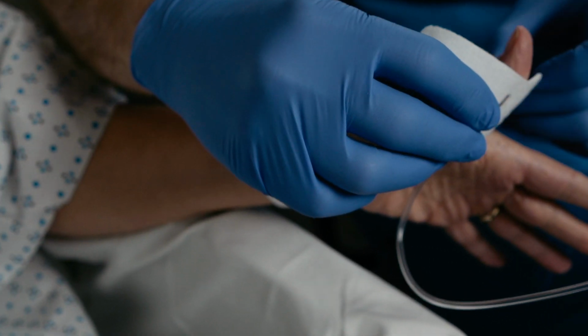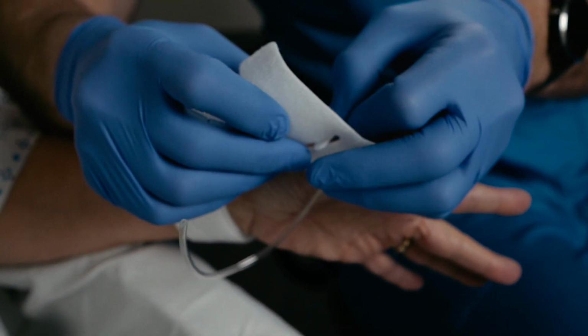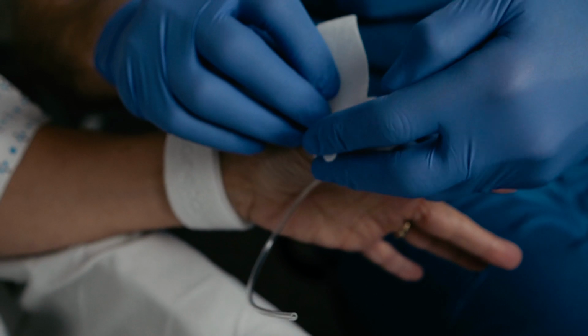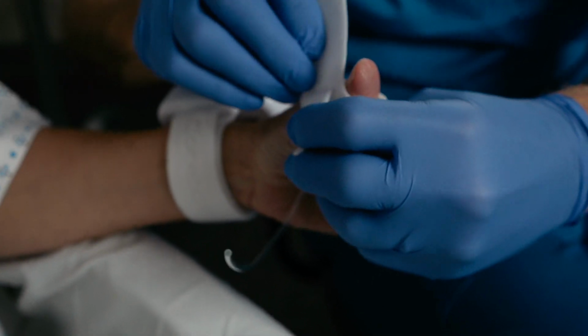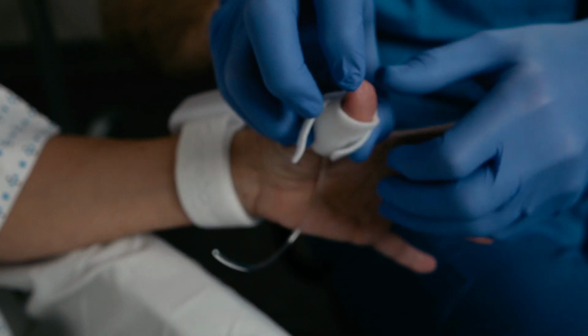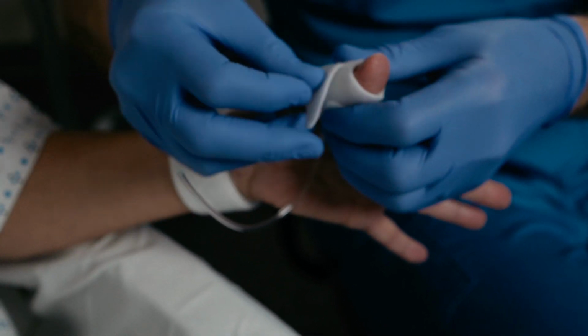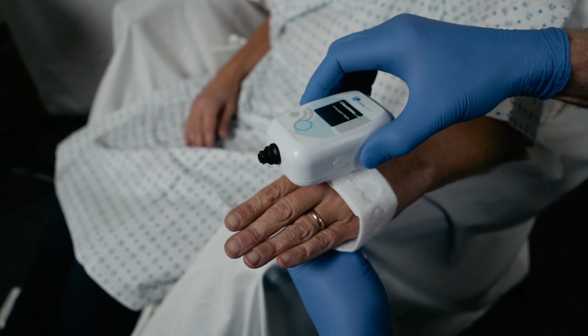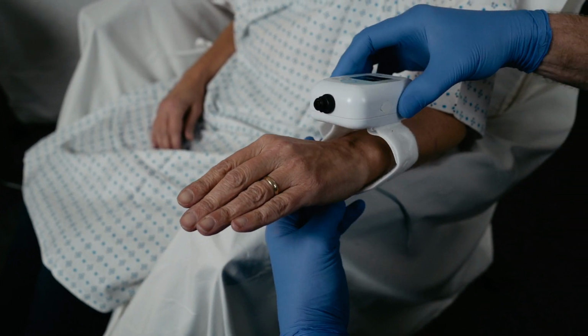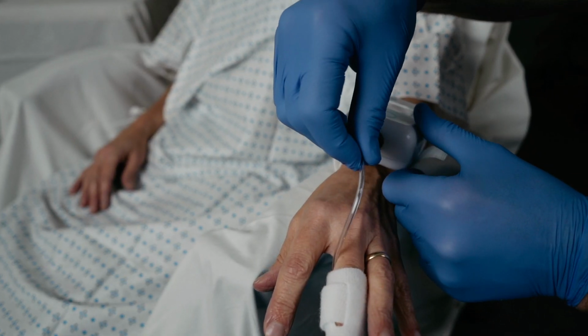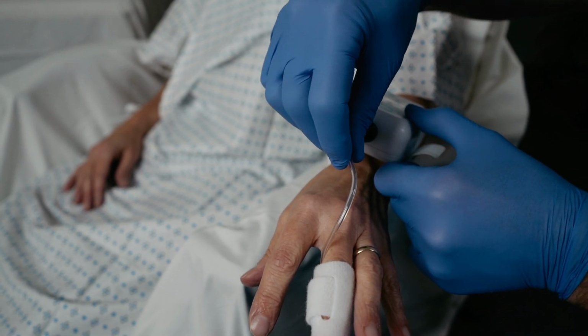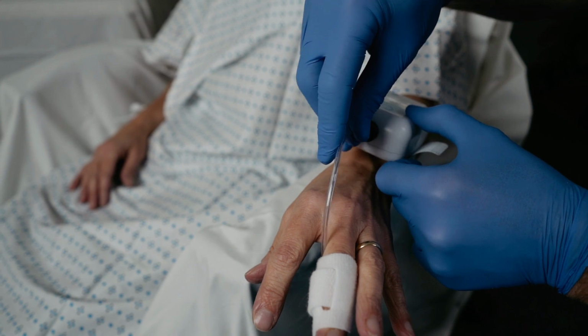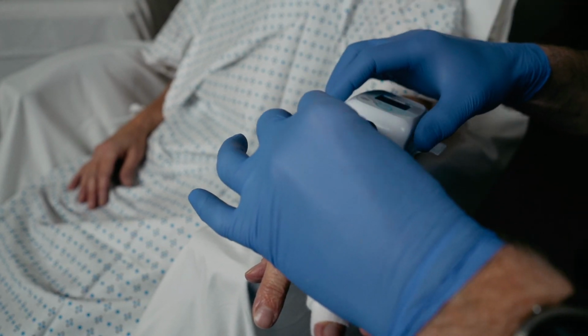The finger cuff may be used on any well-perfused finger, or in manual calibration mode, you may also use the thumb. Note that this is not an ideal location when using automatic calibration mode. Now attach the wrist unit to the patient's wrist using the Velcro straps. Insert the tubing from the finger cuff into the nozzle of the Caretaker device. Note that the tubing can be cut to any desired length with a pair of scissors.